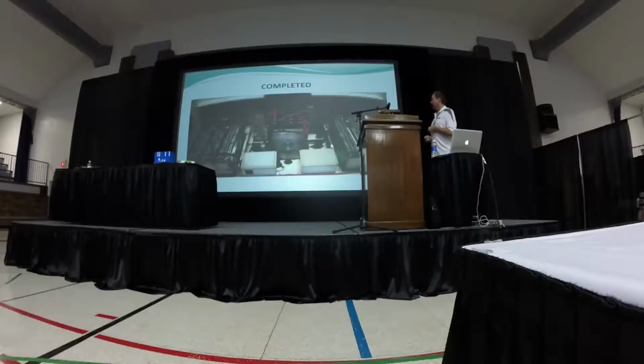We actually had to go in here and pull all the batteries out. That little white line there is a piece of Nomex. We had to go around all the inside of the battery trays and around the top and insulate with Nomex to keep it from shorting out. It's not a lot of current, but like I said, it's enough to trip the GFI in the motor controller and you'll get a fault.